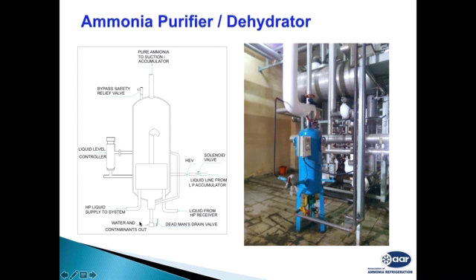But if you are not able to maintain those pressures, your system suction pressure is lower and discharge pressure is higher, then you have to install ammonia purifier and air purger systems. You can install air purgers common for your multiple chillers, so that one purger may serve 4 or 5 chillers. It is the same with the ammonia purifier system. You can install one for multiple chiller systems and connect it to a different chiller maybe every 2 months.